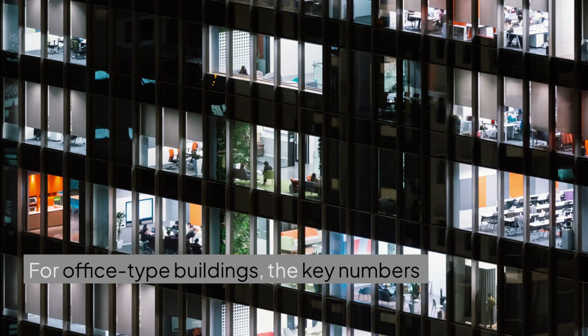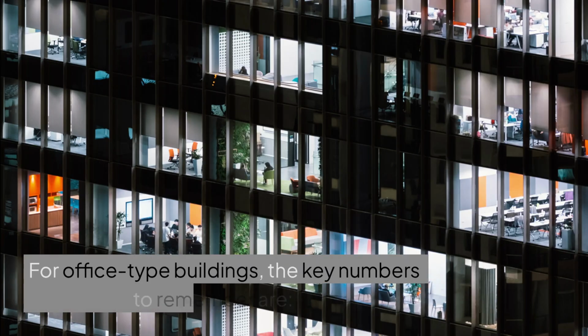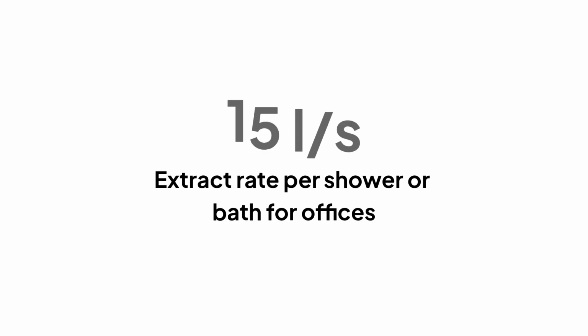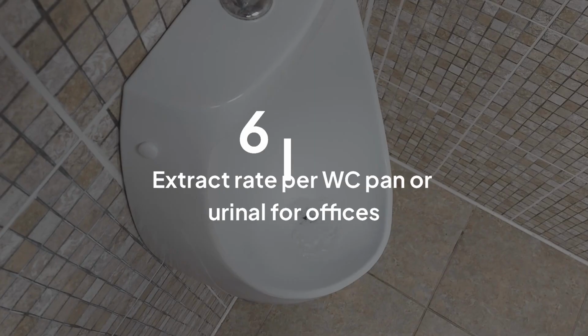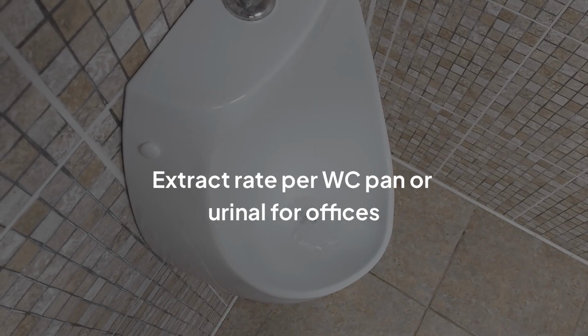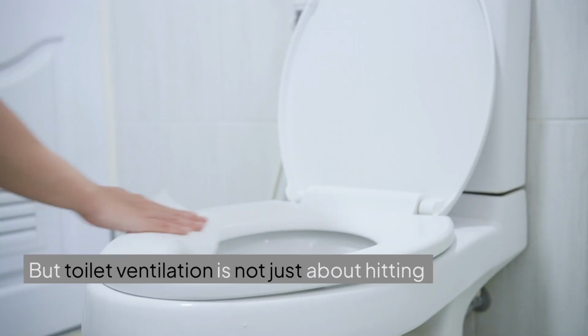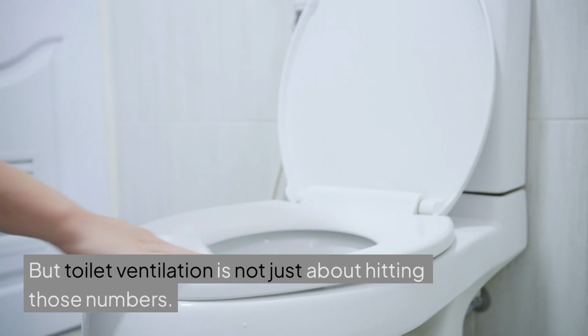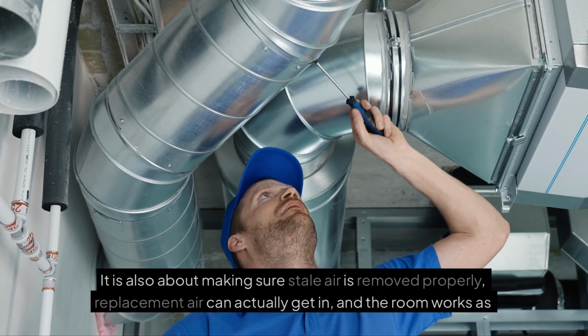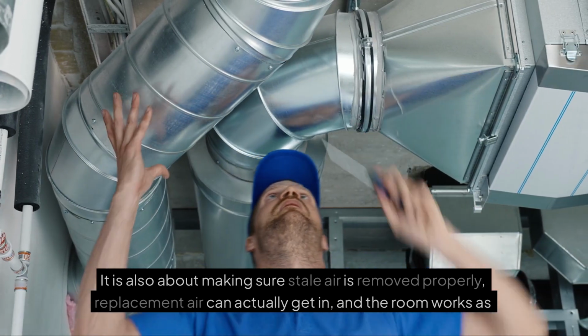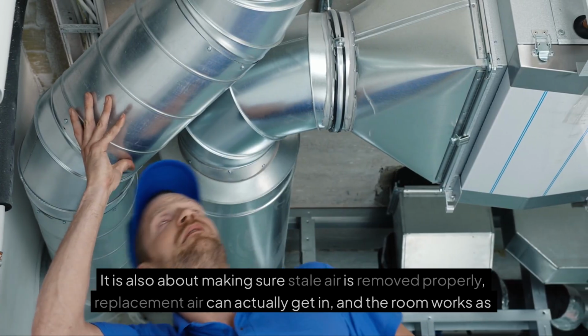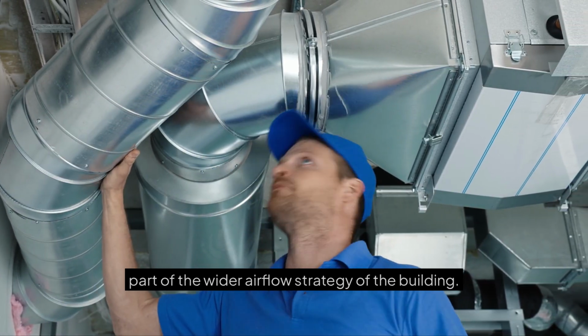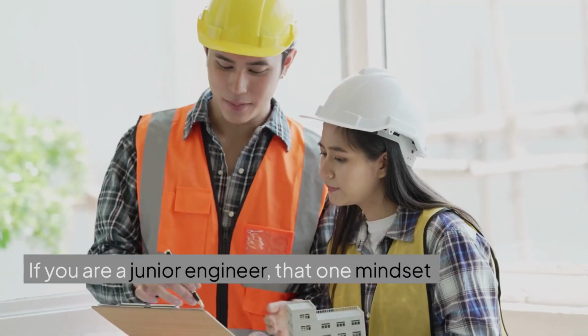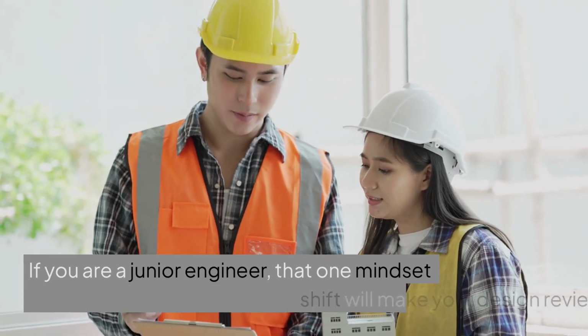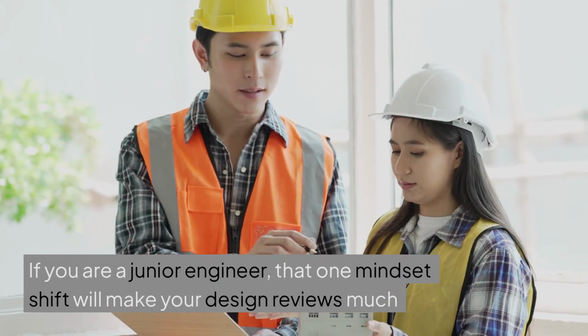So the simple takeaway from this video is this. For office-type buildings, the key numbers to remember are 15 litres per second per shower or bath, 6 litres per second per WC pan or urinal. But toilet ventilation is not just about hitting those numbers. It is also about making sure stale air is removed properly, replacement air can actually get in, and the room works as part of the wider airflow strategy of the building. If you are a junior engineer, that one mindset shift will make your design reviews much stronger.